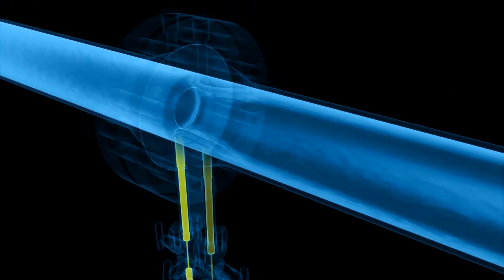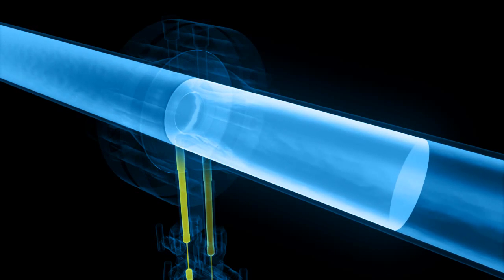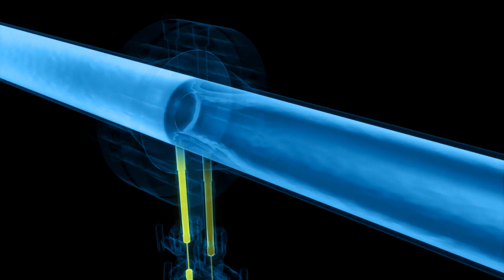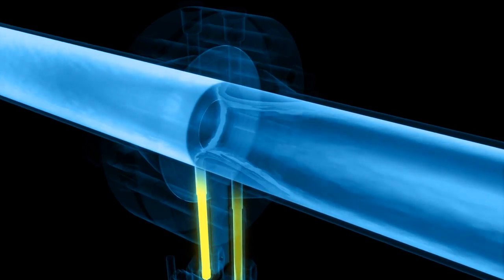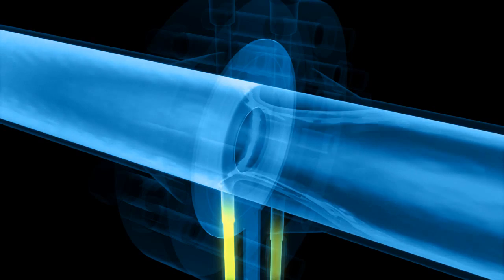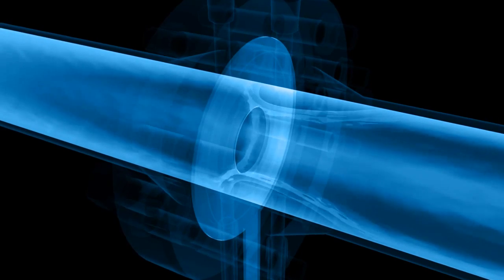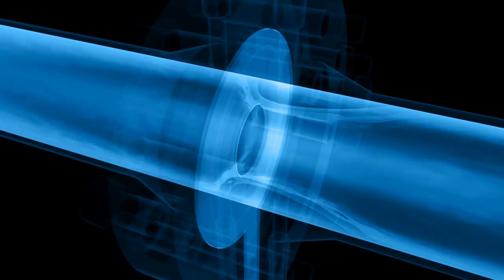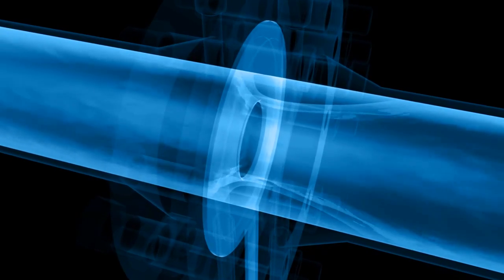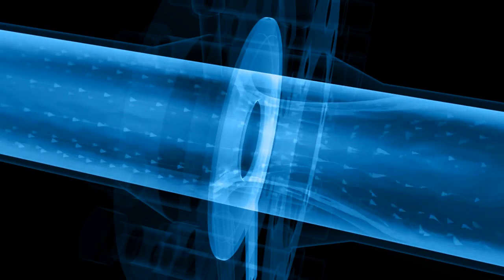This pressure difference is directly proportional to the flow velocity, and thus to the mass and volume flow in the pipe. The higher the flow velocity, and the resulting drop in pressure around the orifice plate, the greater the differential pressure measured. In numerous industrial applications, the orifice plate covers many needs of flow measurement technology. However, other designs are available for certain measuring tasks to minimize undesired effects, such as excessive pressure loss or abrasion of components due to solids carried in the fluid.